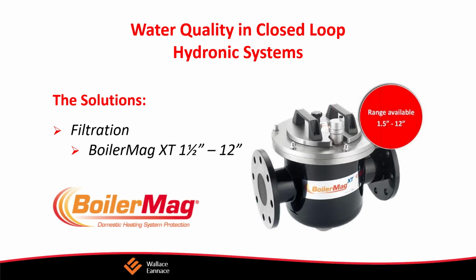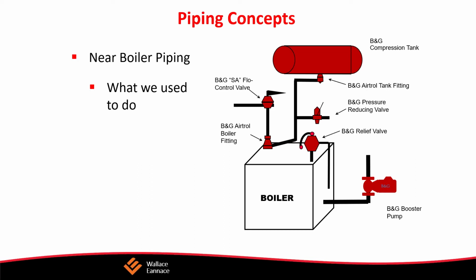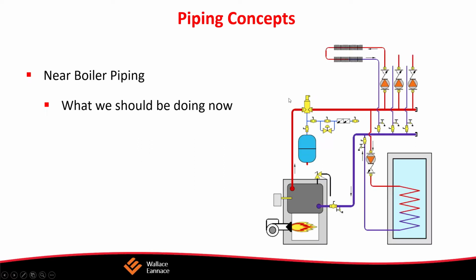And this is a section out of a Lochinvar manual. In the installation section, it says: install a field supplied strainer filter to prevent damage to the heat exchanger caused by debris from entering the system piping. Okay, common sense. Everybody's been doing that. When installing on a pre-existing system, a strainer filter capable of removing debris left in the system is recommended. On the next line, it says: install a field-supplied magnetic separator in a heating system return line as close as practical to the boiler per the manufacturer's instructions.